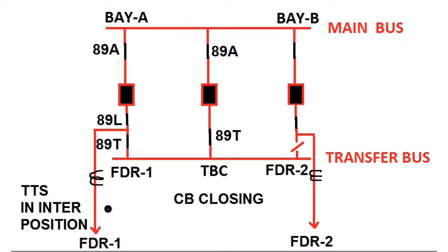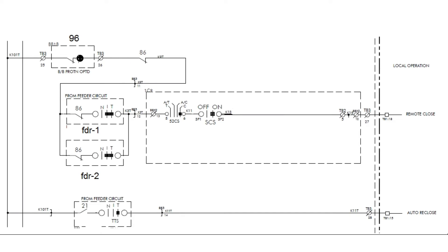Now the TTS switch position can be moved to the transfer position. If any fault arises in this feeder, the relay will sense this fault and it will transfer the trip through the TBC breaker. Let us now discuss the closing of the TBC breaker. This diagram shows the remote close operation circuit from the TBC — that is the transfer bus coupler breaker.